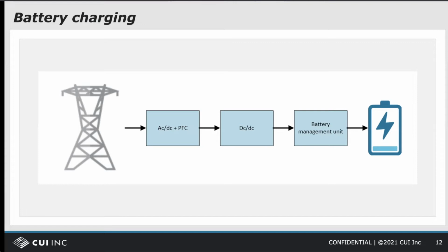The output of the AC to DC stage is a high voltage DC that is often fed into a DC to DC stage. For safety and efficient charging, battery charging follows a specific voltage and current profile. During certain portions of the charging cycle, the battery may require constant current or constant voltage. The DC to DC stage takes the high voltage from the AC to DC stage and converts it to the battery voltage according to the charge profile. And last, there's a battery management unit that controls the process and whose purpose is to protect, monitor, and balance the battery cells. It monitors the state of health and the state of charge of the battery cells and balances them to optimize their life and efficiency.